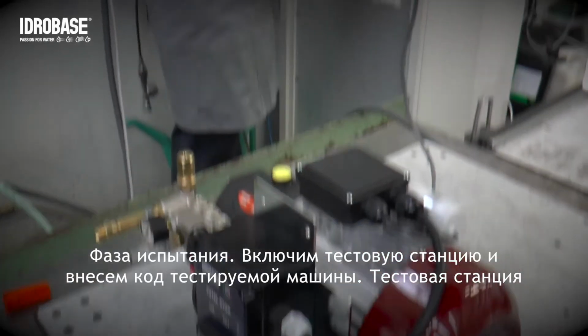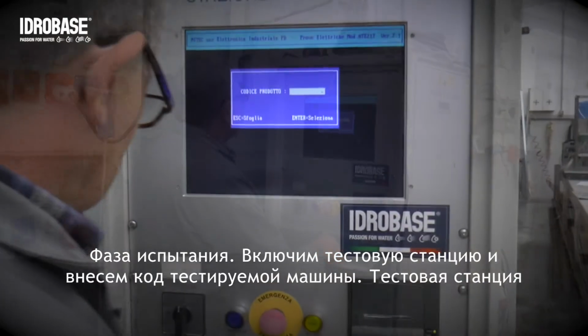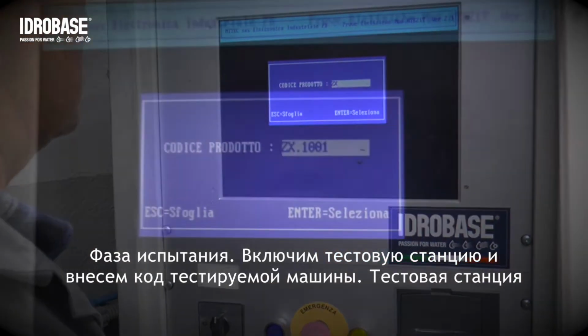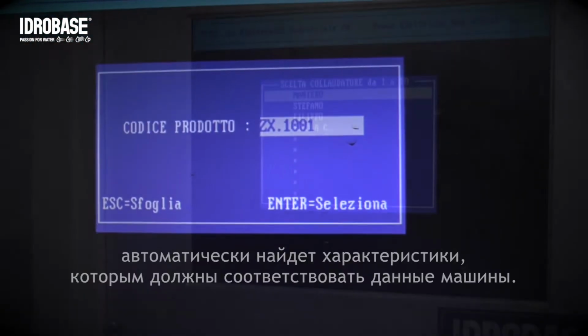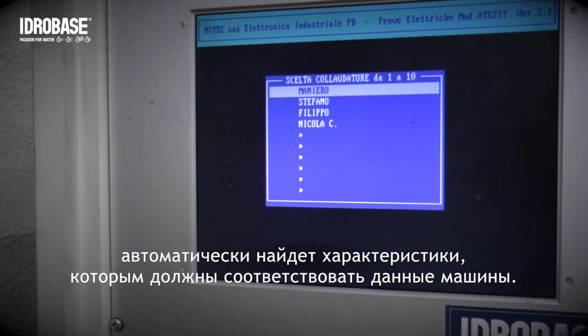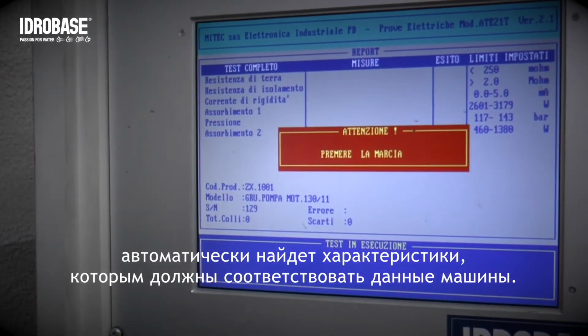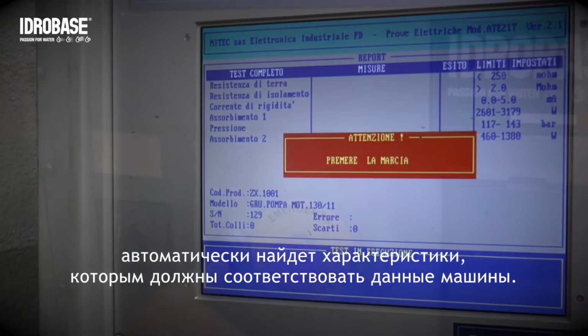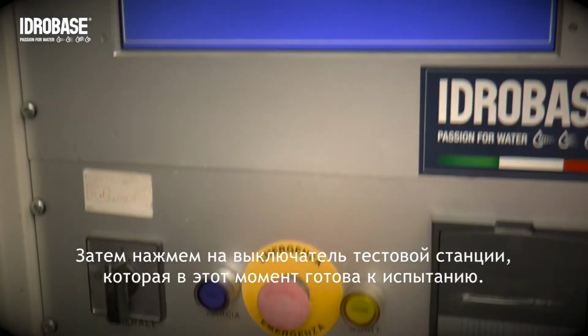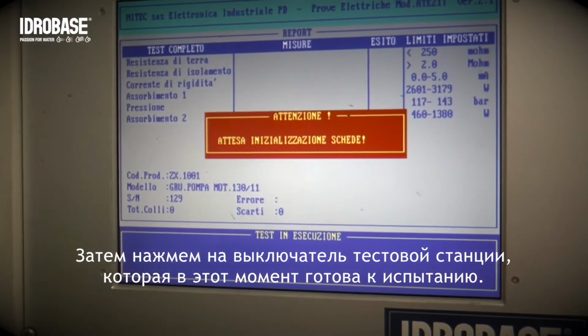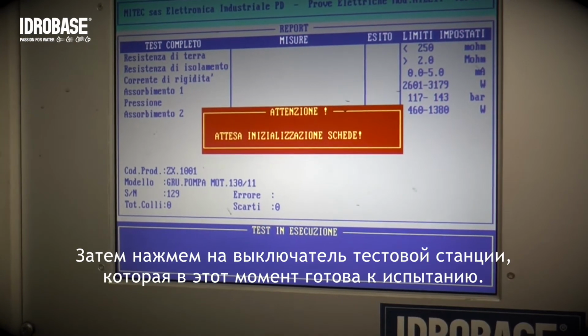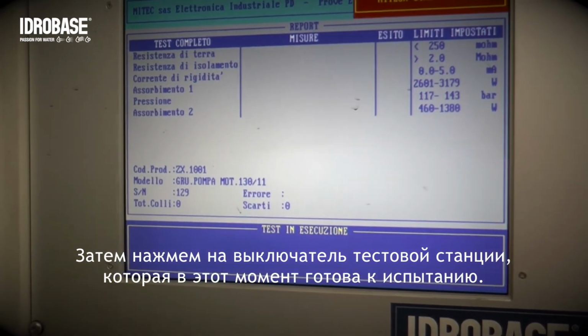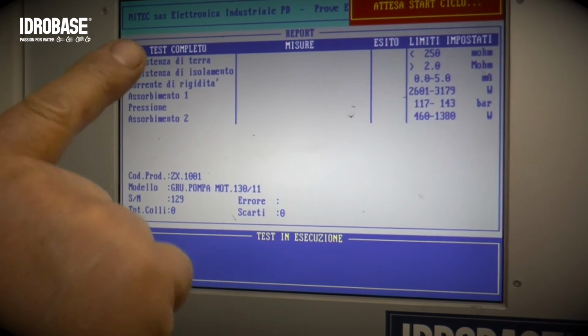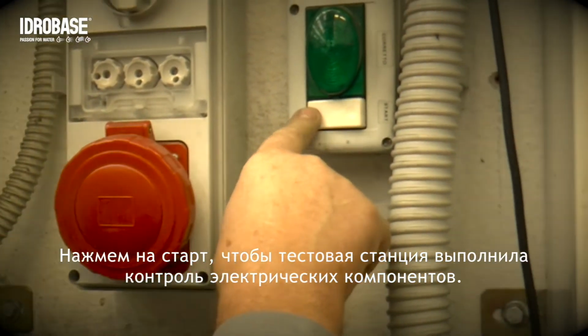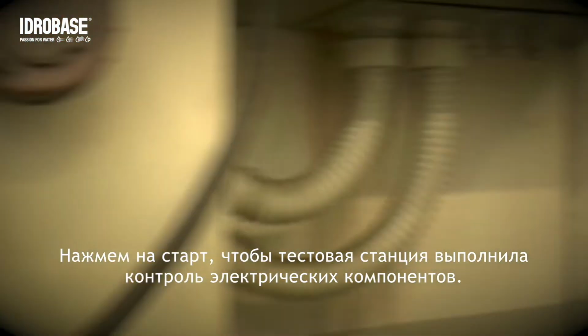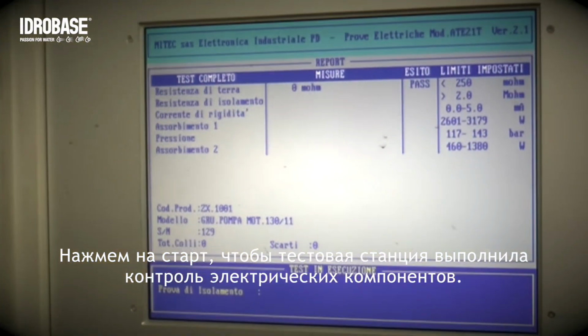As regards the testing procedure, turn on the test station and insert the machine's code. The test station finds automatically the data corresponding to those of the machine. Press the Run key of the test station, which is now ready for the testing procedure. Press the Start key so that the test station can perform the electrical checks.